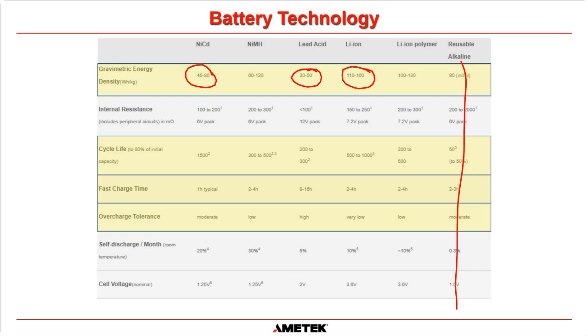Cycle life is also important. For a NiCad, you can get 1,500 cycles for the life of the battery. But for a lead acid battery, it's about 200 to 300 cycles for the life of the battery. Now, for a UPS in standby applications, that's usually absolutely fine. You'd be very unusual to see 200 to 300 power failures on a North American UPS. If it's a 20-year life, that's 10 power failures a year, which would be very unusual. But the data is there to say, if you're expecting a lot of cycle life, then NiCad's the way to go. And you can see that lithium ion, the two different technologies, they give you more cycle life as well.